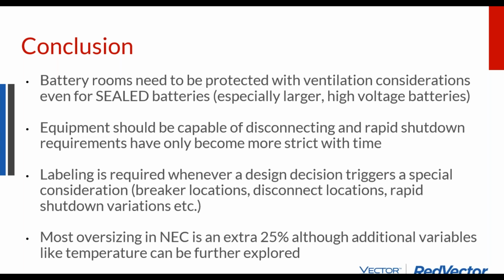Equipment should be capable of disconnecting. The disconnects are required when you get more than 5 feet away. Rapid shutdown right now is not required for batteries, but it is for solar. Your labeling requirements: you pretty much have to put a label whenever there's something special going on. If you're doing a load side connection, you need a label. Most sizing is adding an extra 25%, although with solar specifically, when you're not using electronics to control the output of the array, then you have to have an additional 25%.